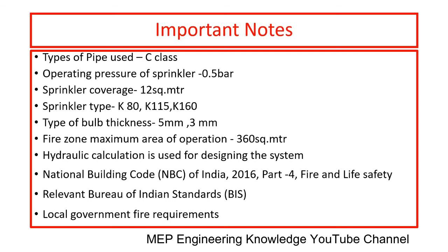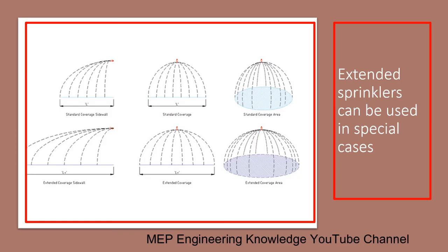Hydraulic calculation is used for designing the system to identify the pressure requirement and the water flow. National Building Code NBC of India 2016 Part 4, Fire and Life Safety, is a standard reference document for authority approval. Similarly, BIS will be used. Next, the local government fire requirements have to be checked and considered during designing. It varies from state to state or place to place, depending upon the geographical location. Though we have standard sprinkler types, we have extended sprinklers as well. In special cases, we can make use of extended sprinklers, which will have more coverage area.